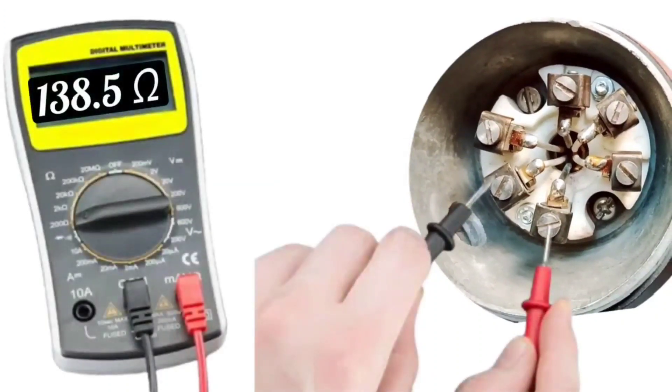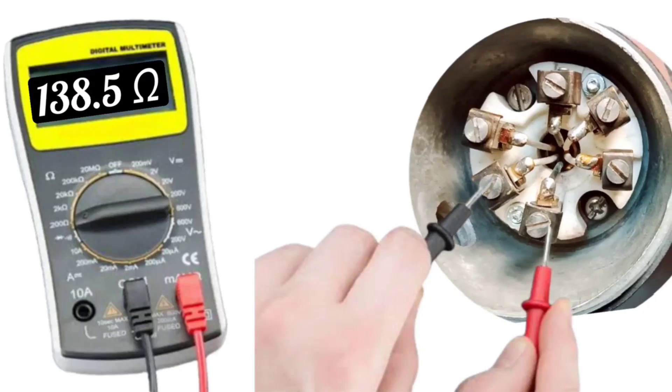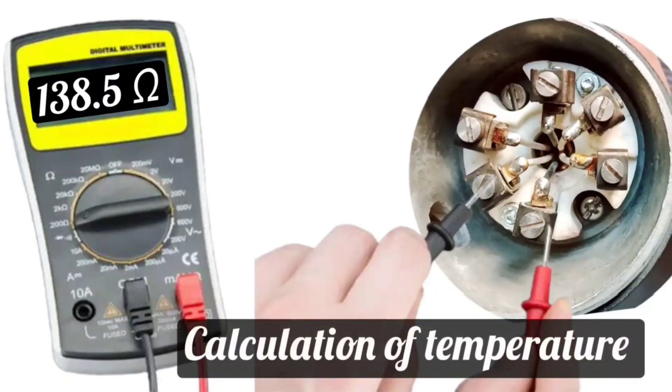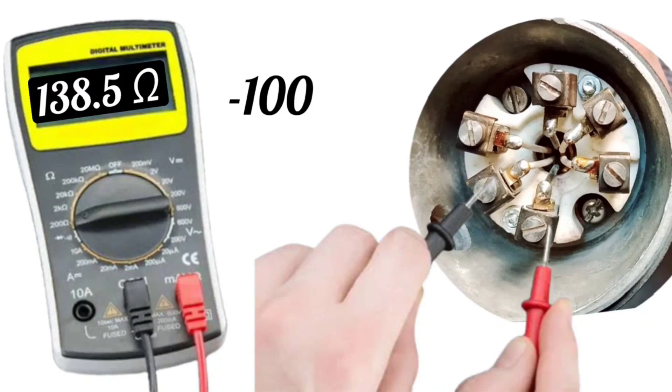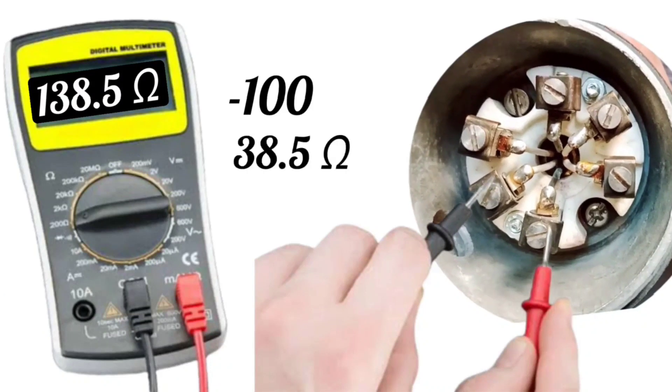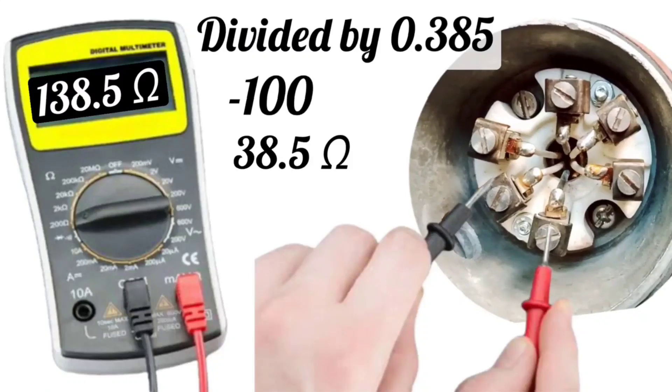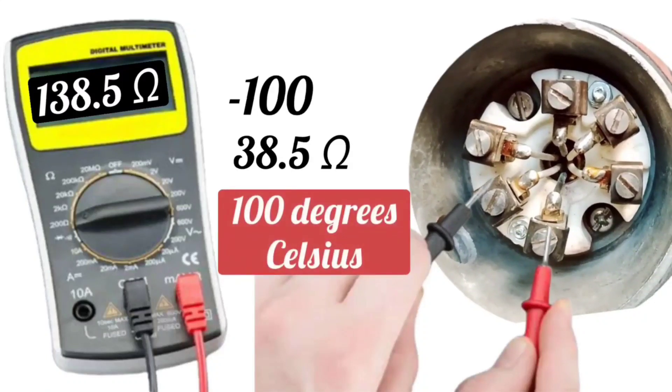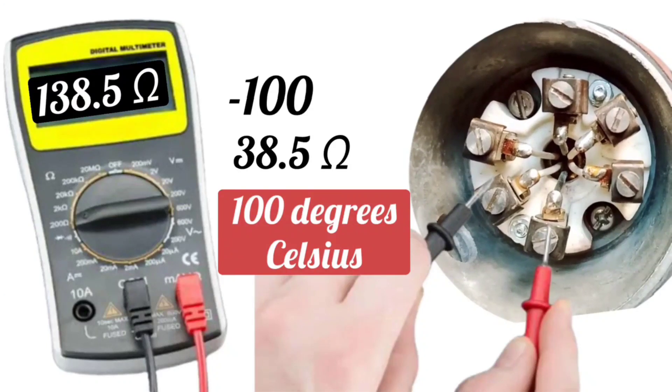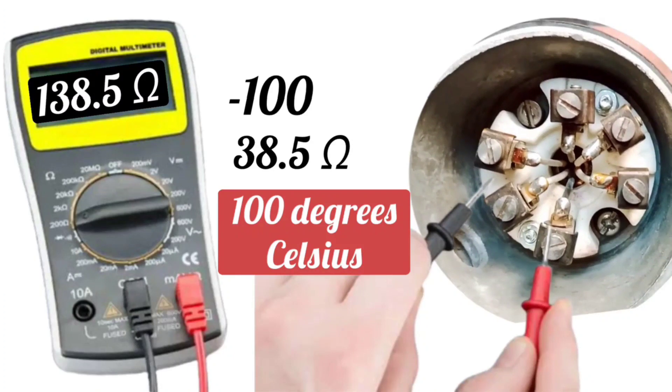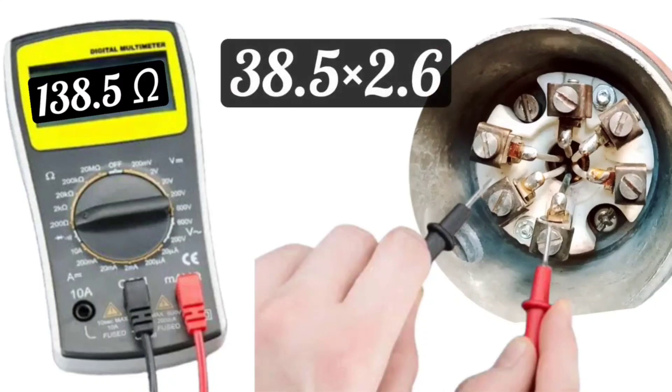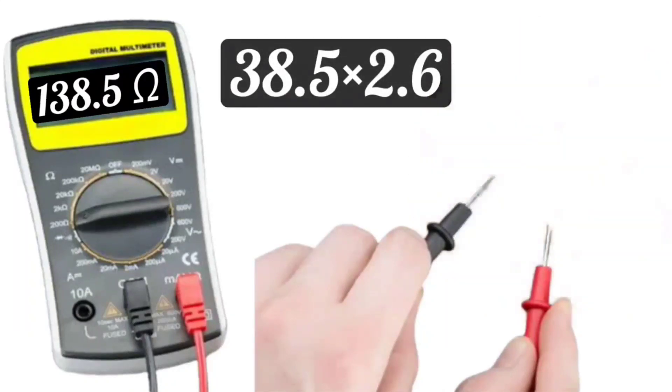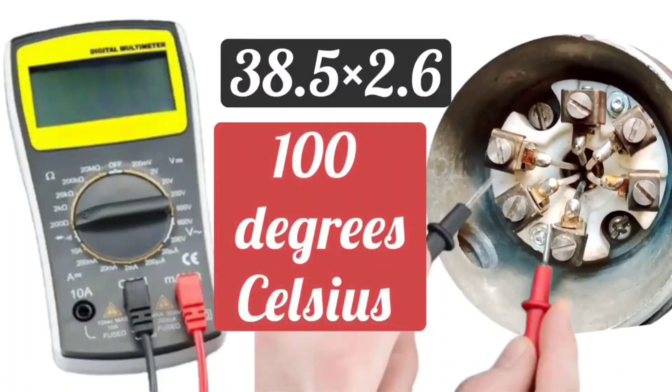For example, if the resistance of RTD is showing 138.5 ohms, then calculate the temperature. Subtract 100 from 138.5, it will be 38.5. When we divide it by 0.385, it will be 100, which means 100 degrees Celsius temperature will be on that place. If resistance is showing 138.5 ohms, let's solve it with other method. If you multiply 38.5 by 2.6, then it will also be approximately 100 degrees Celsius. So it's very easy to calculate RTD temperature.